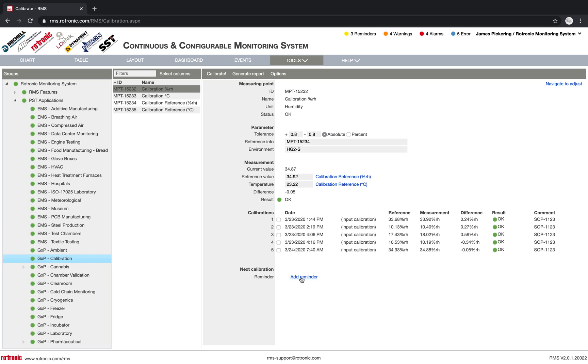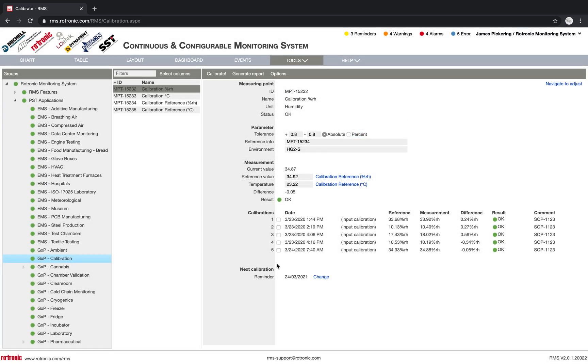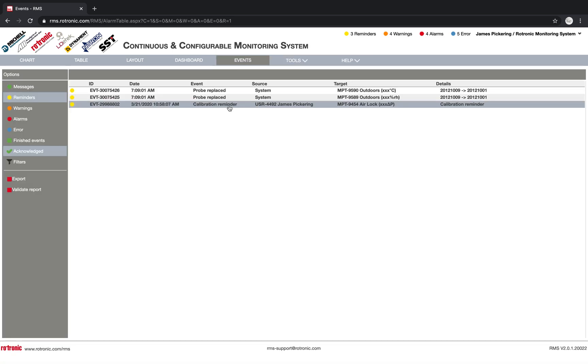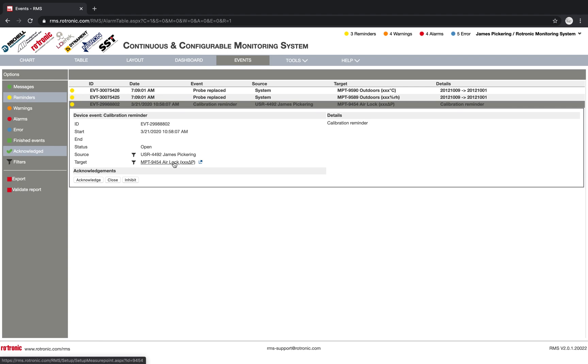So then afterwards, we can simply add a reminder, when is the next calibration due? So I'll click on here, and then I can define when it is required. I simply click here on okay, and then we have a date that appears. As soon as this date comes, then a new reminder will come up. So if I click here on reminder, I can see that here, there is a calibration reminder in the system. So I need to calibrate this device here, the MPT9454, which is my airlock, which is differential pressure. I would need to calibrate that now.